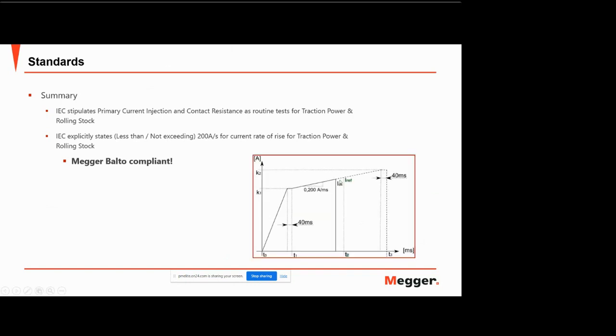As you can see here in the graph, this is a typical graph we get with the Megger Balto. Between T0 and T1, you can see the high current injection. And then from T1 all the way up to T2, we slow the rate of rise so that we make sure we correctly get the trip current, which is the IDS, the current for direct setting, which is your trip current.